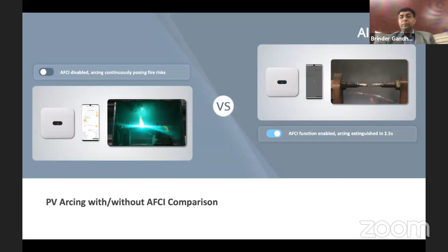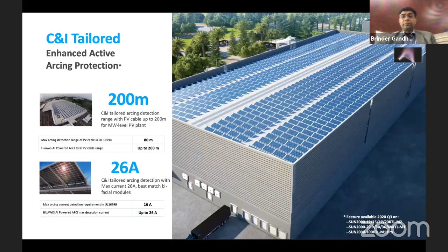We have also improved the length of the arc fault protection, because Huawei inverters are also used for large scale projects. As per the UL standard, UL 1699B, the required length for DC cable is 80 meters, but with our tailored solution, we are able to offer a 200-meter length for detection range, and it can also have a maximum current of 26 ampere, which includes the bifacial modules in the detection.